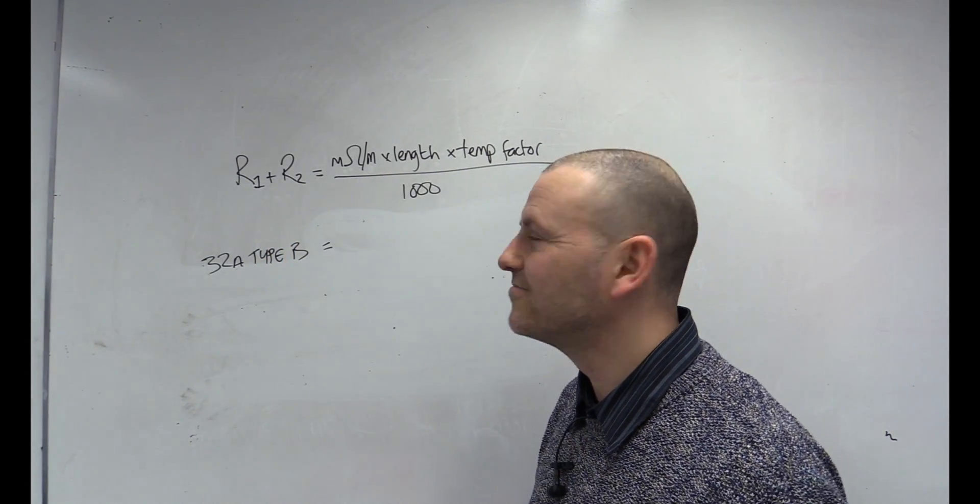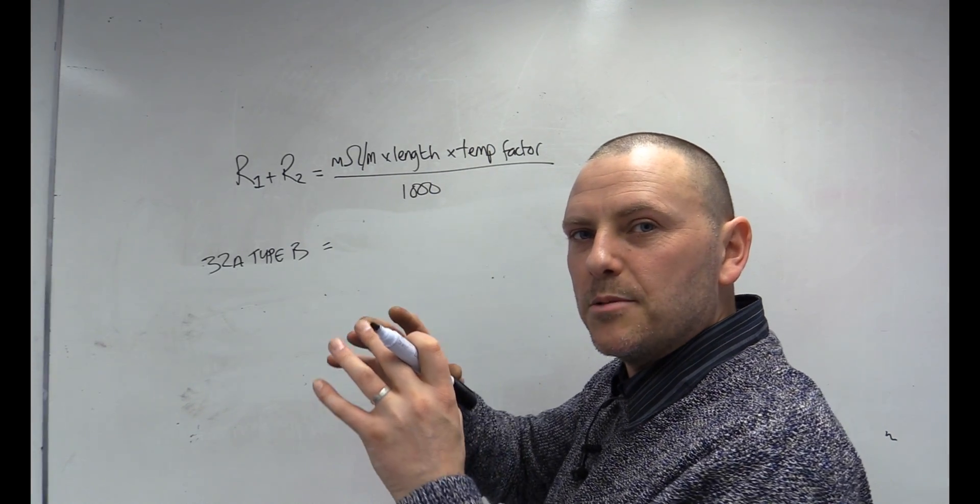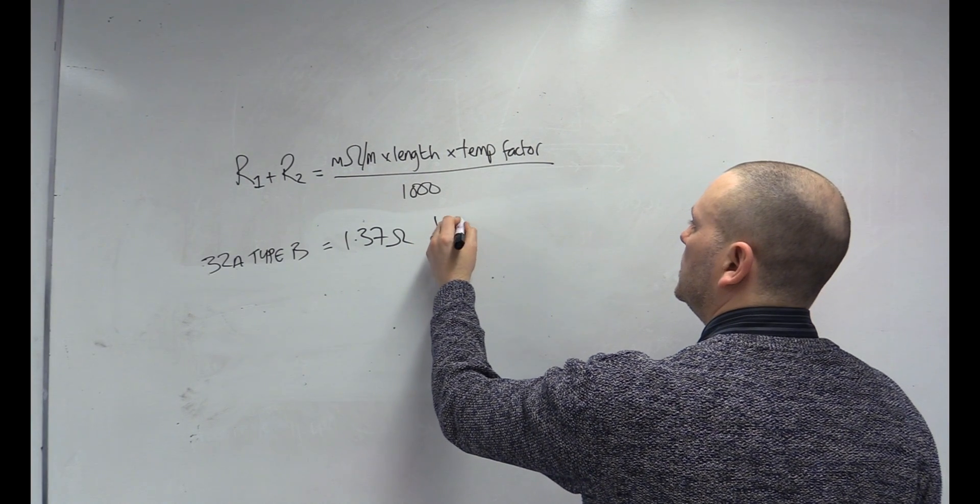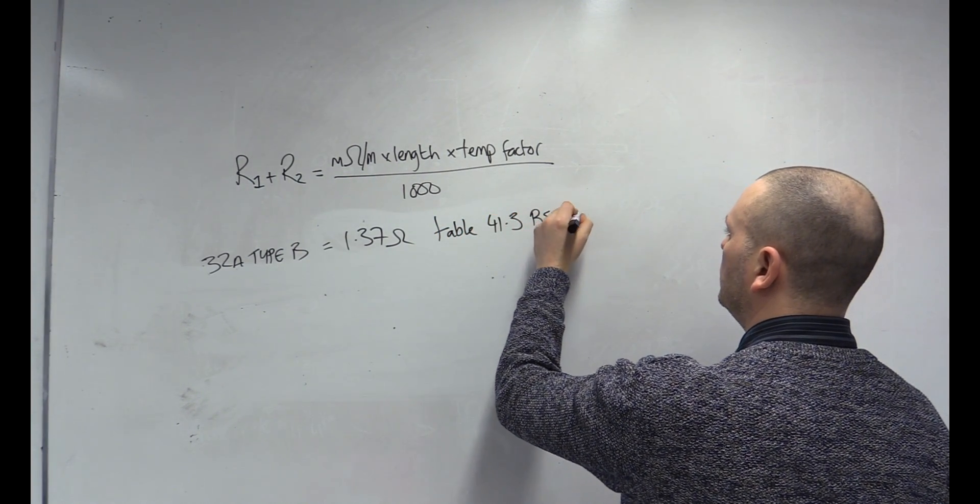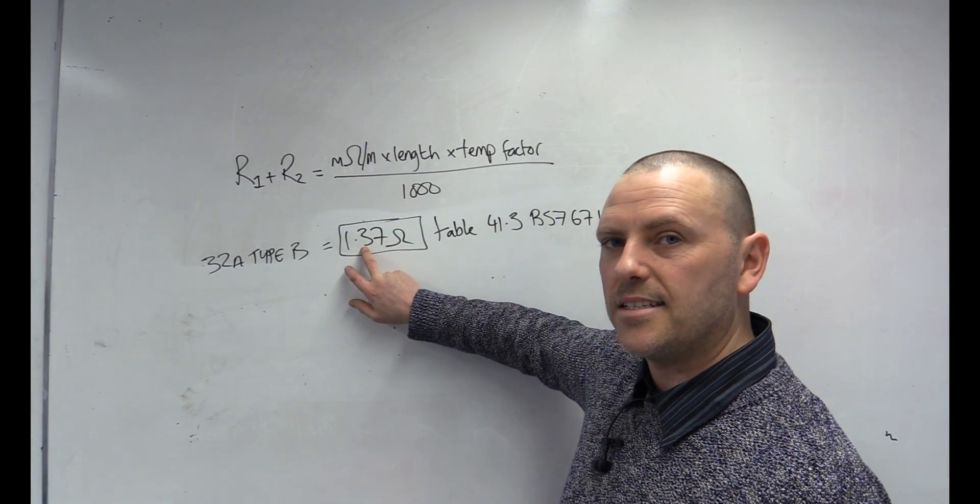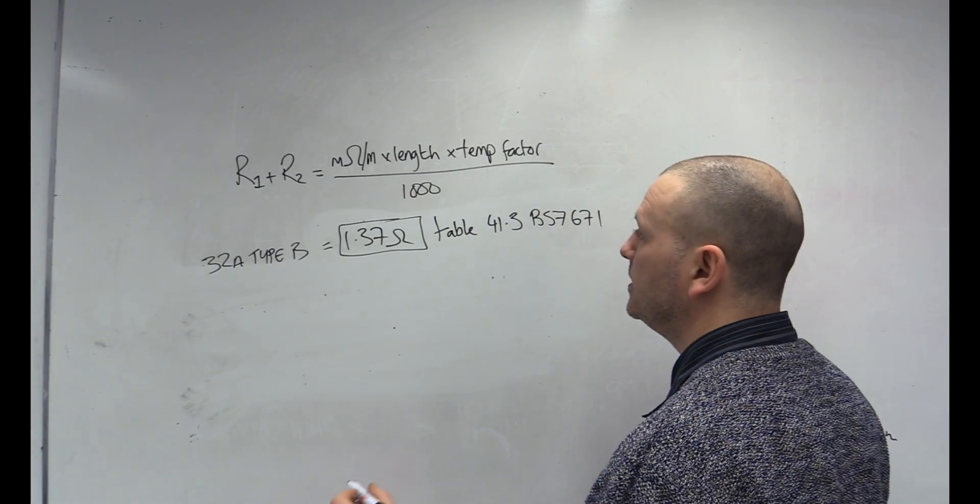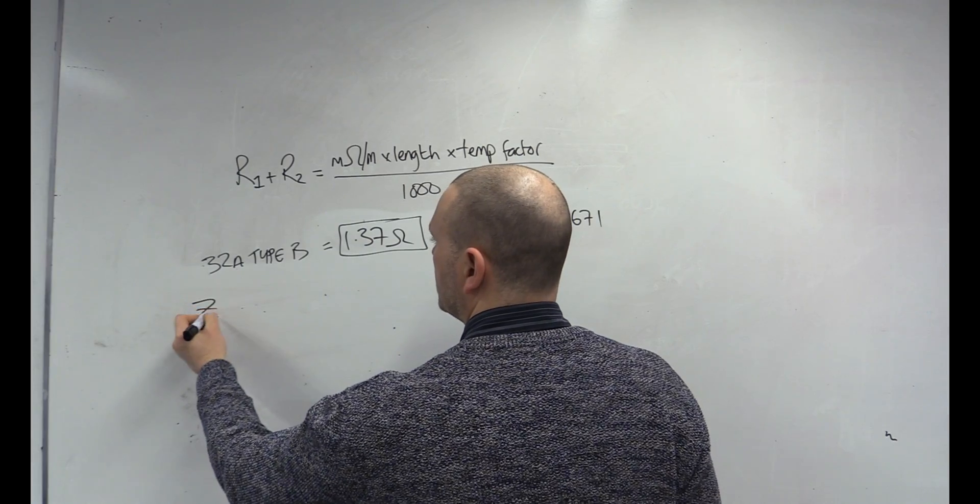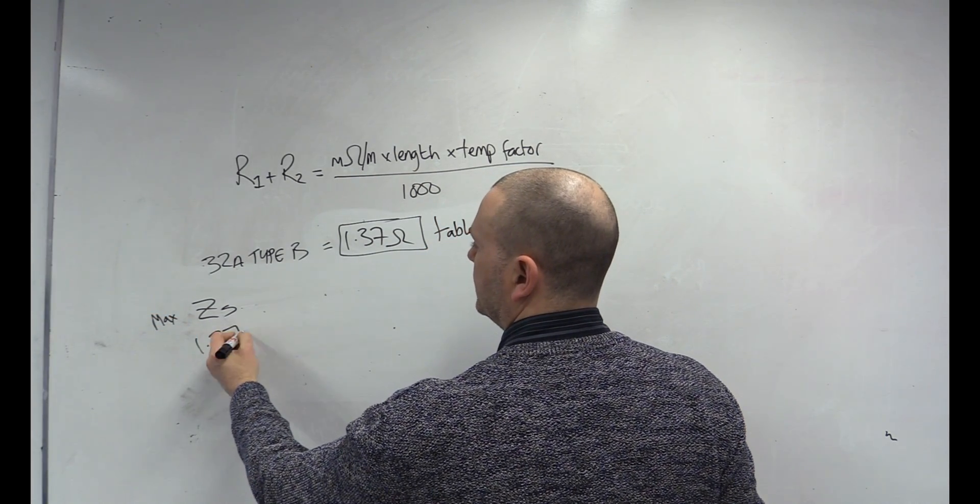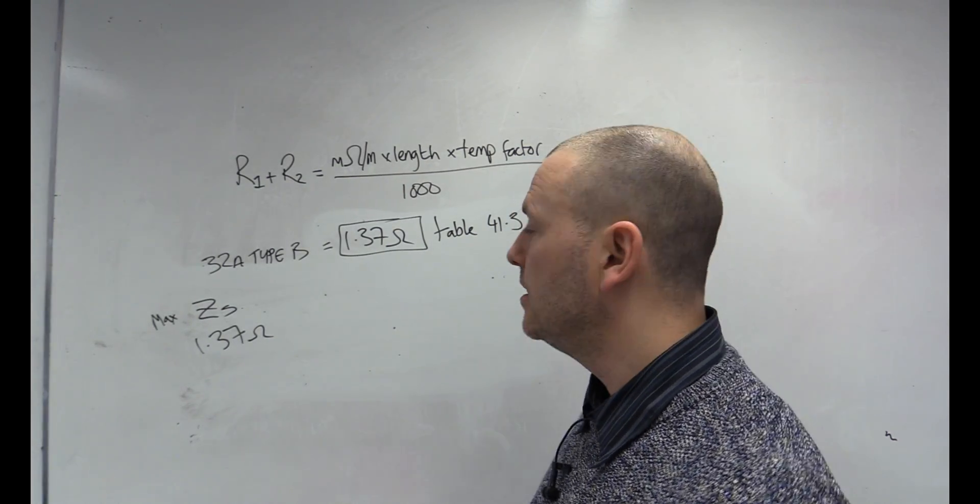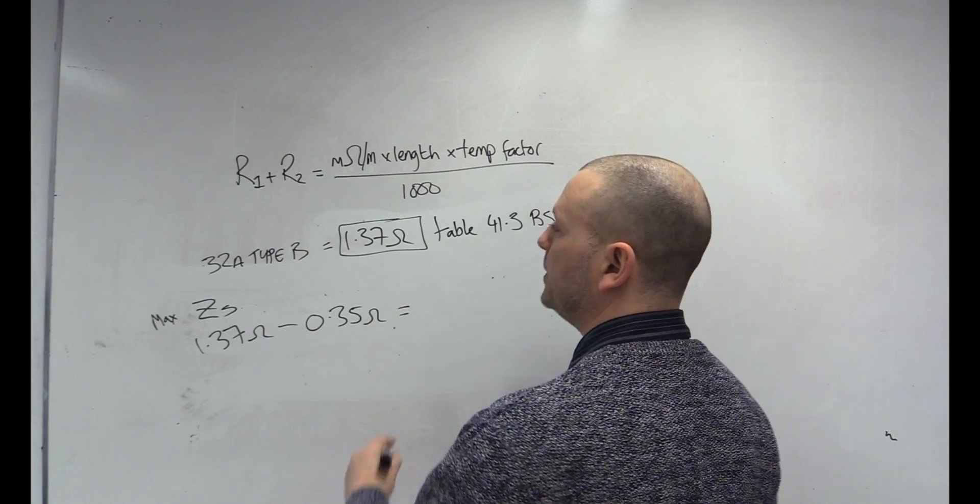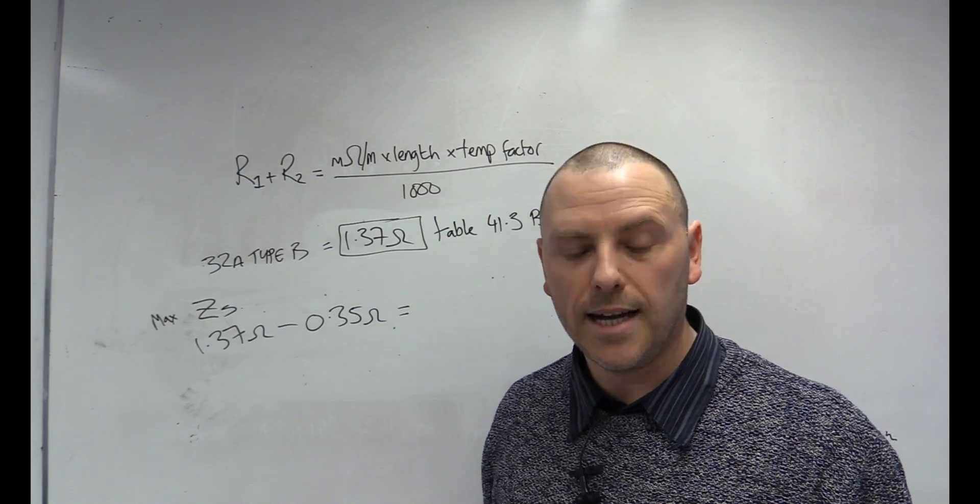Now, the maximum ZS, when we're in design mode, we need maximum ZS at that temperature. So, in this case it's 1.37 ohms, and you can find that, table 41.3 BS7671, around probably page 60ish, I think. But this is our kind of maximum ZS. Then, if we know our maximum ZE for the property, we can start building an equation to calculate our maximum R1, R2. So, if our max ZS is 1.37 ohms, and let's say we've got a TNCS earthing arrangement, so that's at a maximum 0.35 ohms, we take away that 0.35 ohms, what we'll be left with is the maximum internal loop that we're allowed.